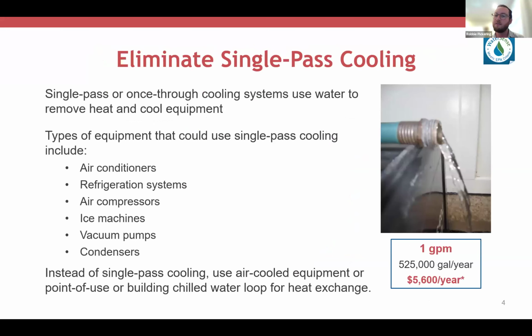So a lot of equipment within laboratories requires equipment cooling, and that can sometimes be provided through single pass cooling. Single pass cooling, if present, really has the potential to be the greatest single water waster within your facility. And so when you're starting out with looking at water management, this is a really great place to start. Single pass cooling is a situation where city water is plumbed to a piece of equipment to remove heat from it. After use, it goes right down the drain.